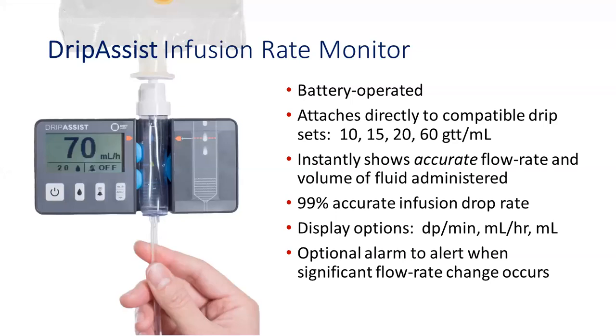So as I mentioned, we built the device so it wouldn't require a lot of training. There are no sub-menus. You're looking at this device with me. You can see there are 4 buttons and that's it. That first button on the left turns the device on and off. That second button is where you would select the drip set that you're using. The 3rd button, as I mentioned, is that optional alert. And then that 4th button tells you whether it's milliliters per hour, or drops per minute of volume. Just toggle through.